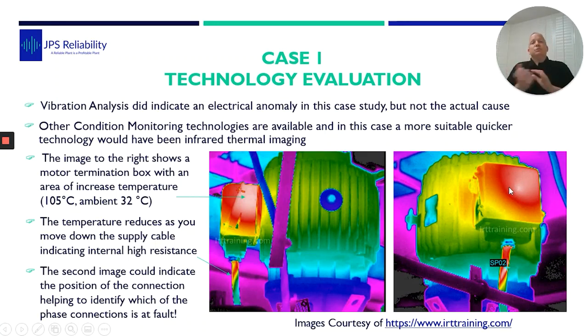So this is to say, don't just use vibration, don't just use thermography, don't just use ultrasound. You've got to use them all together. And that's how, if I did have a thermal camera, you'd have picked it up bang straight away. But through vibration, I did find out what was causing it.